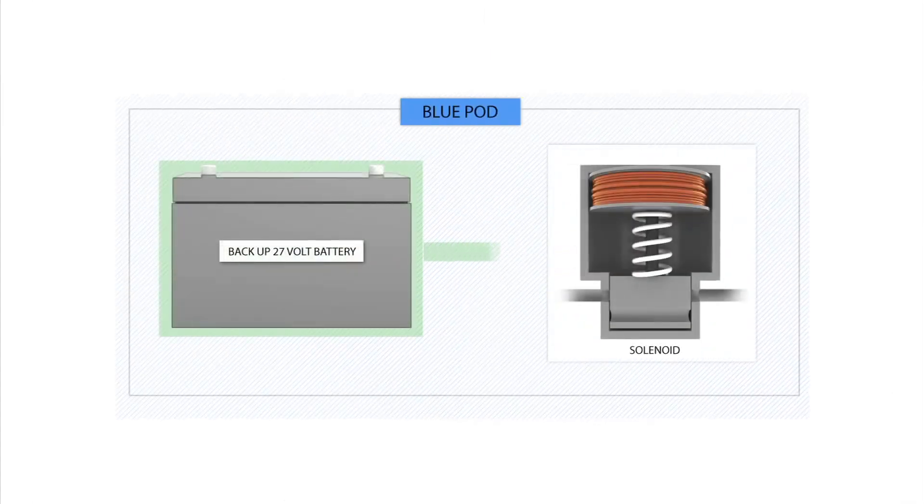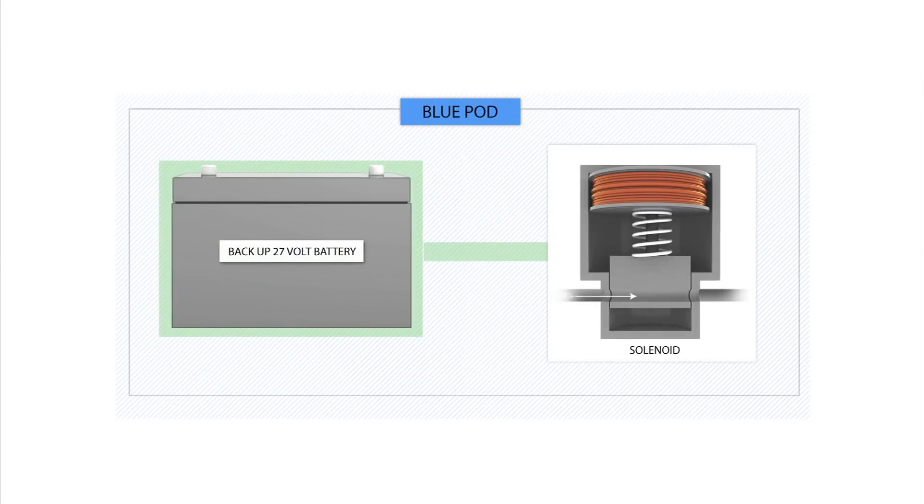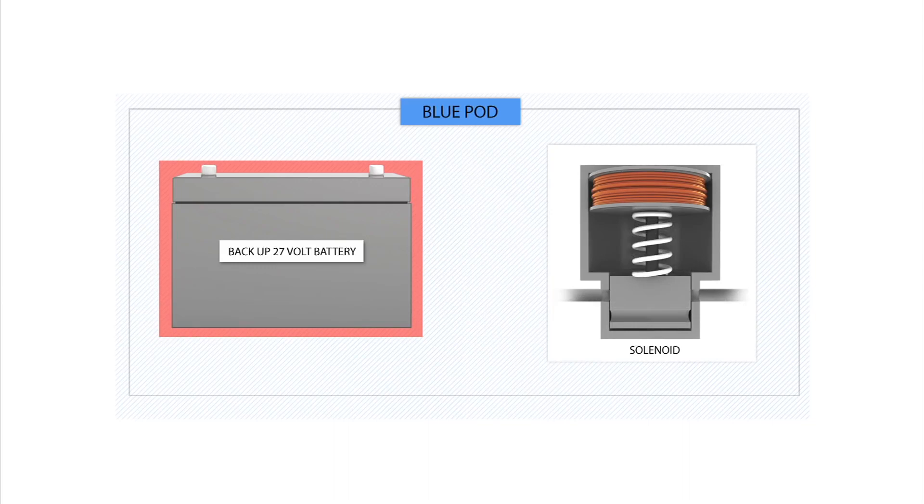However, evidence indicates the Blue Pod had been miswired at some time before the BOP was lowered onto the seafloor. This caused the pod's 27-volt battery to drain and made it impossible to operate the solenoid valve for the blind shear ram on the night of the accident.